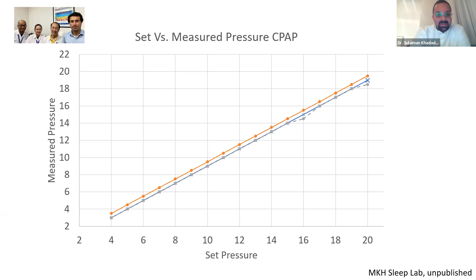And this is just at 5-minute intervals at each pressure. We've also run devices, if you go to the next slide, for over 72 hours. And since then we've generated a ton of other data that we've shared with Philips. Here again, I've just shown the data for pressure at 20 at different humidity levels: 5, 3, and 0, or an HME filter.